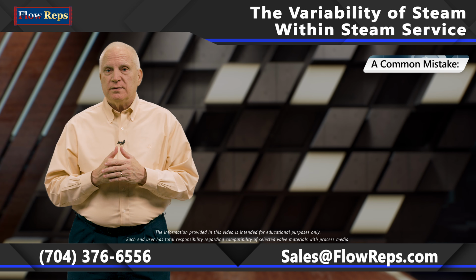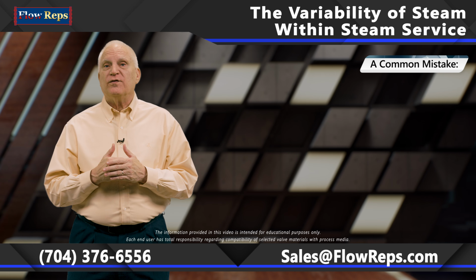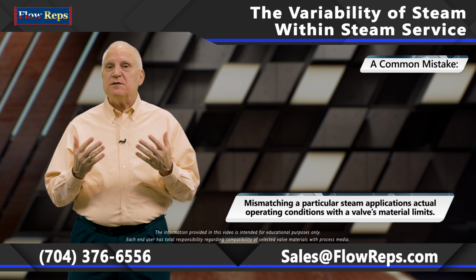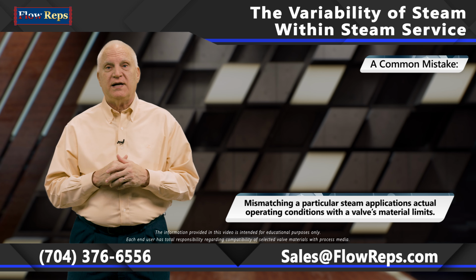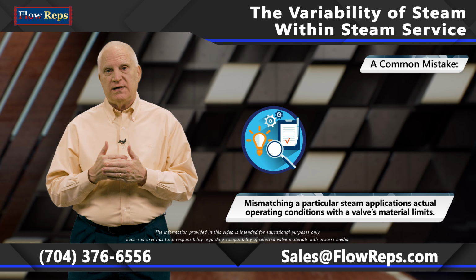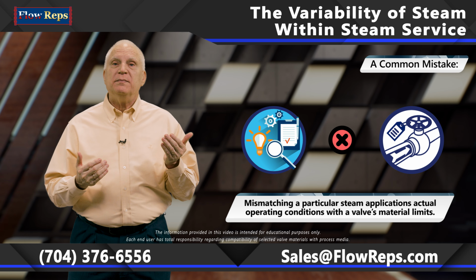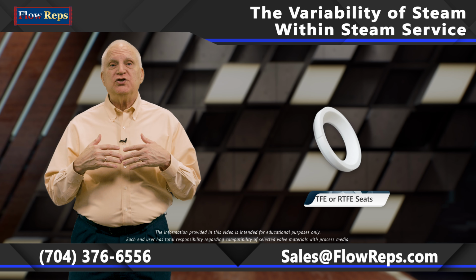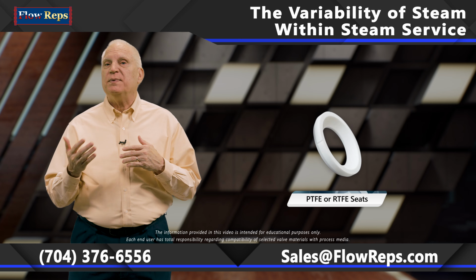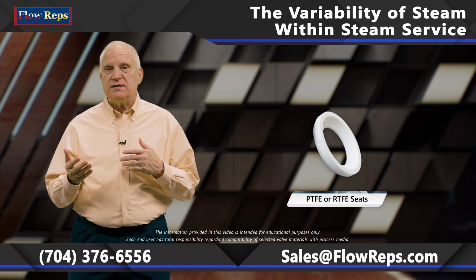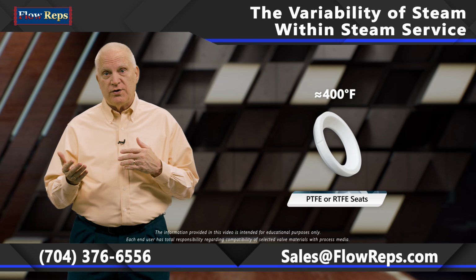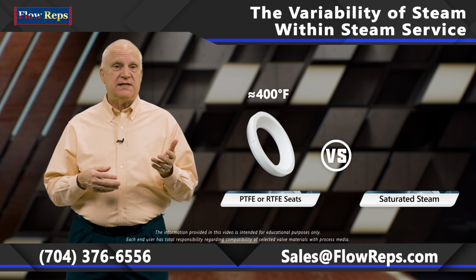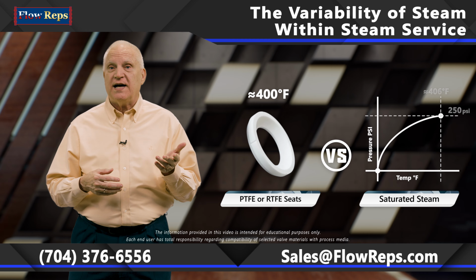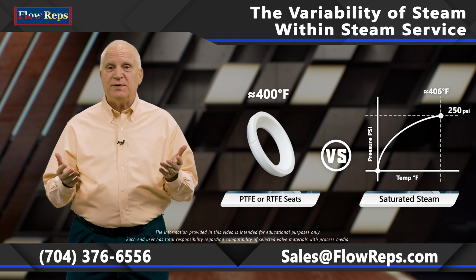But although simple, a fairly common mistake for valve selection is mismatching a particular steam application's actual operating conditions with the valve's material limits, such as using a soft-seated valve with standard PTFE or RTFE seats, which start to deform around 400 degrees F, while saturated steam at just 250 psi can already reach that temperature.